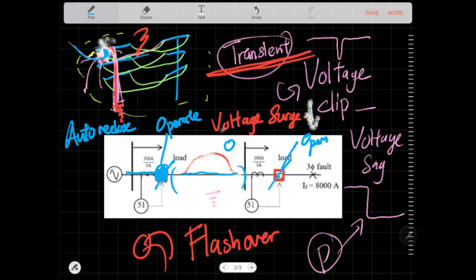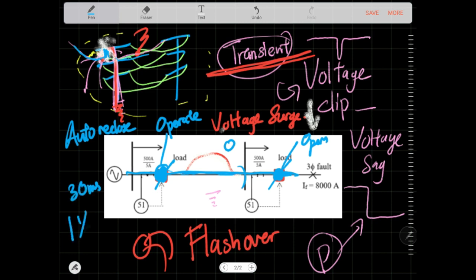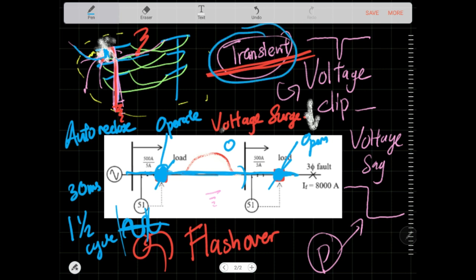With auto-reclose there is no earthing isolation — the breaker simply opens and then auto-recloses. This happens within about 30 milliseconds, or roughly one and a half cycles of the electrical frequency. The line is normalized again. That's why it's called a transient fault — it happens for a brief moment and is normalized. You get a voltage dip because for that one and a half cycle the line is temporarily dead, then it energizes back.